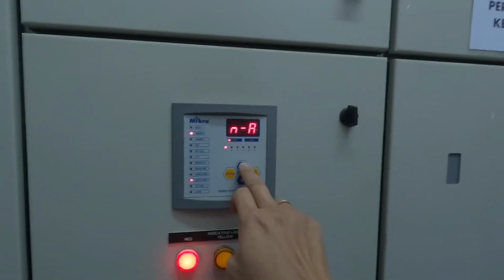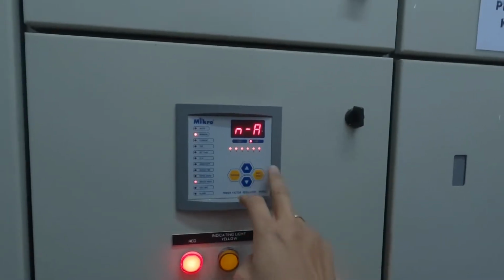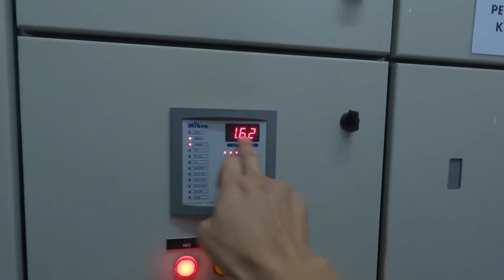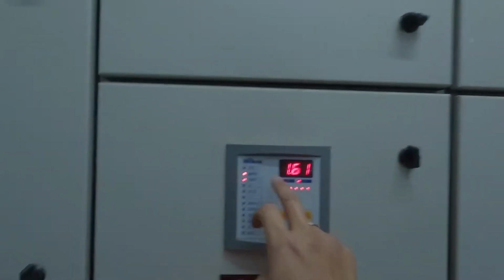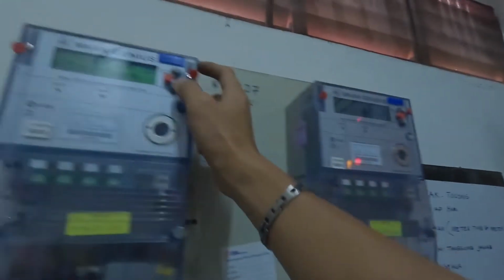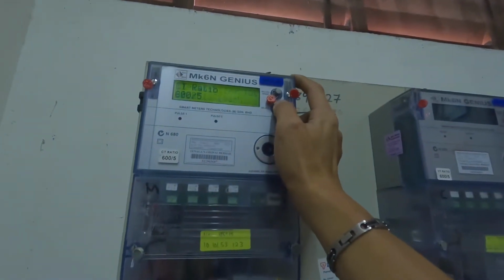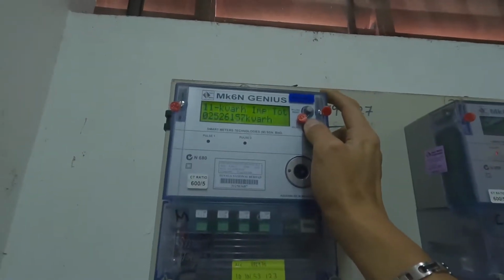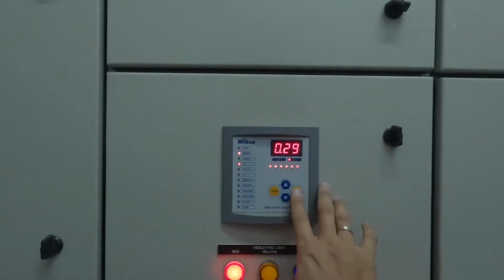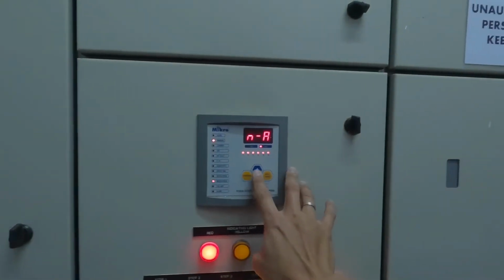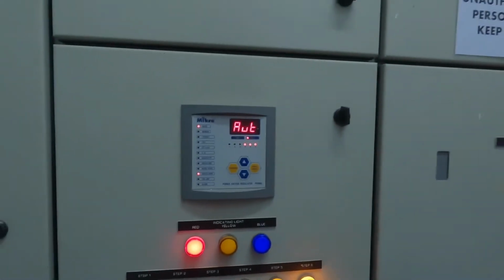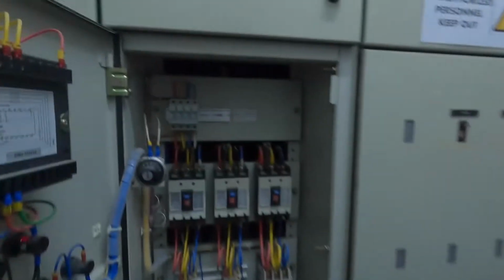Go to manual mode. Okay, on all the capacitor bank, then we check the current consumption, 1.62. Okay, it does go up. Let us check. Okay, consumption increased 100 m. Compensation, no issue. Alright, then the auto back, all the capacitor bank step. Okay, let us check here. Capacitor bank, no cable burn, everything is in good condition.